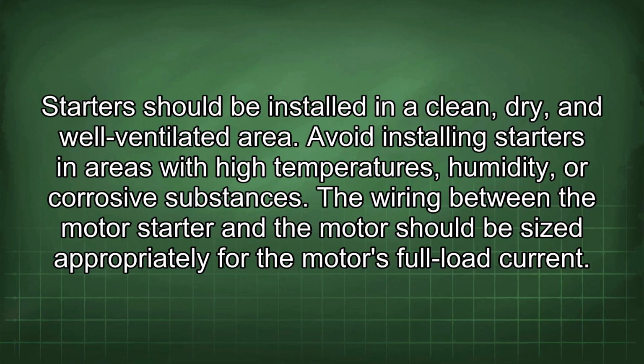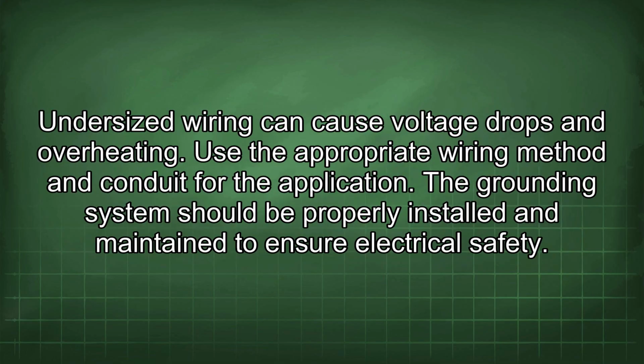The wiring between the motor starter and the motor should be sized appropriately for the motor's full load current. Undersized wiring can cause voltage drops and overheating. Use the appropriate wiring method and conduit for the application.